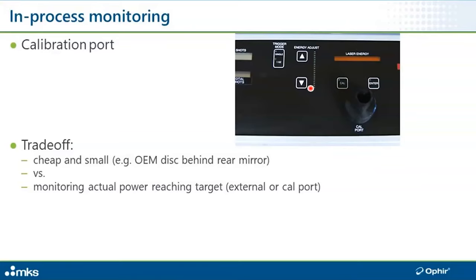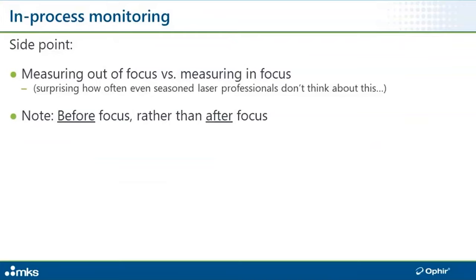So what these customers often do is put a full-blown, full-power sensor inside their system, and periodically, once a day, once an X, the user fires the full power of the laser into this calibration port where it gets measured. The system compares what it's measuring to what it was expecting to measure based on its preset internal settings. And then if needed, it makes internal adjustments. This is kind of the best of both worlds. Again, just an idea.